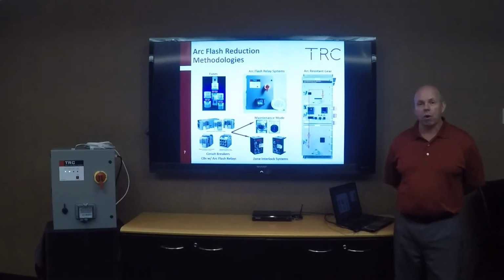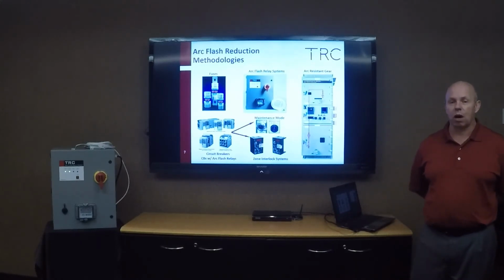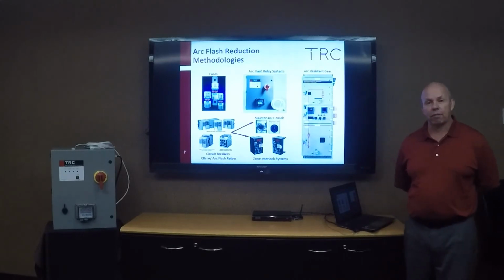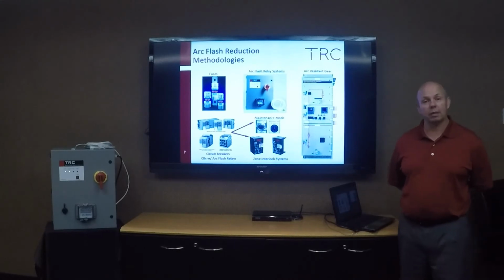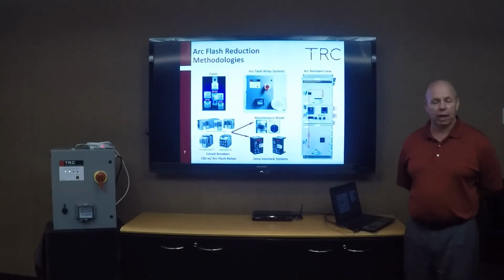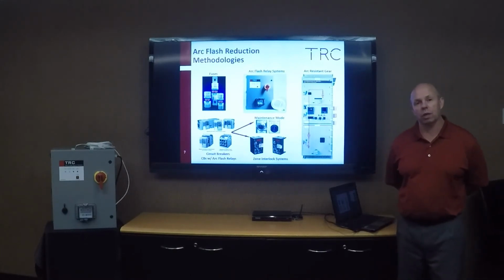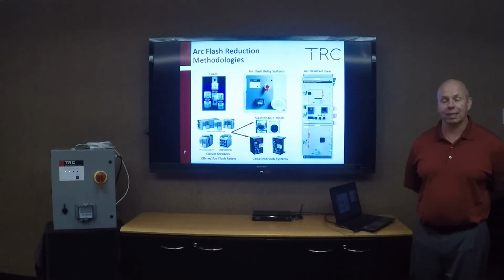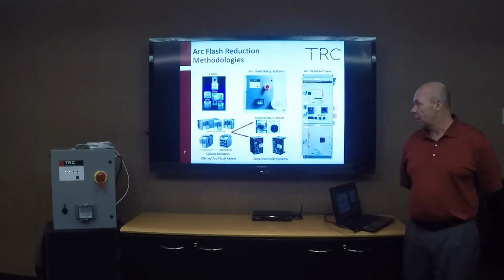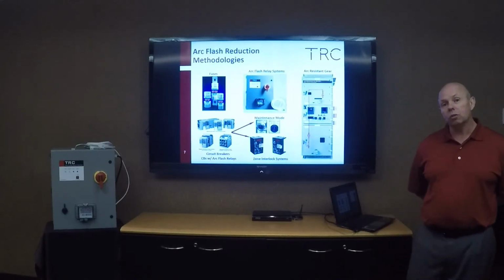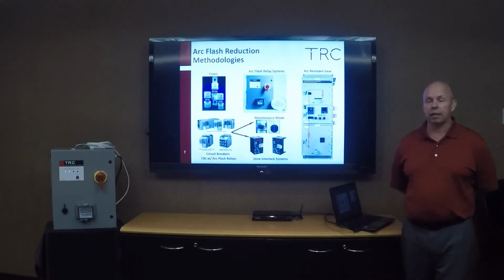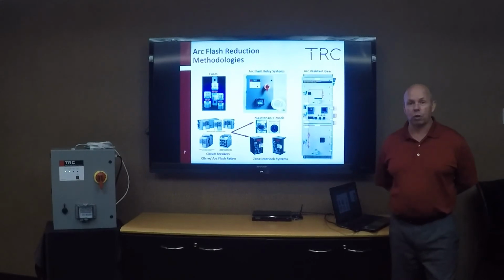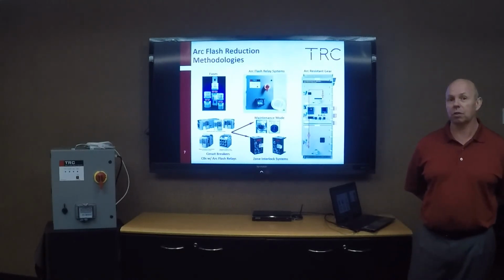And how that's done is when nobody is working on the system, the maintenance mode breaker is off, all your selective coordination is in effect, and whatever incident energy levels are calculated based on the standard overcurrent tripping times of the circuit breakers is in place. But whenever maintenance has to go on inside the switchboard, the electricians or technicians would come over and energize the maintenance mode switch, and what that does is basically turn everything over to instantaneous. So if there's any type of fault current that's detected, that could produce an arc flash event, then it would go to instantaneous and trip very, very quickly. It does reduce the incident energy significantly. However, the downside is that when it is in maintenance mode, you have no coordination between your different circuit breakers, and a fault downstream may take out your whole facility because it goes automatically up to the top breaker.